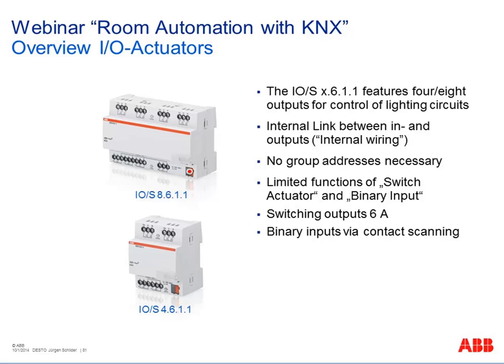We have the same principle as in the room master for linking inputs and outputs, so you can use it without group addresses. But the difference to our room master is that we have limited functions. So here we have no room scenarios and other things. We have really reduced the software features of these I/O actuators, and inside we have only 6 amp relays without manual operation.